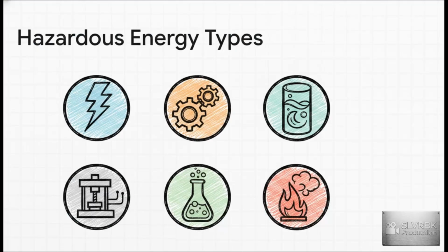Now, when you hear the phrase lockout/tagout, it's super common to picture a breaker box and think strictly about getting shocked. But the hazards are actually so much broader than that. Hazardous energy encompasses mechanical, hydraulic, pneumatic, chemical, and thermal energies. Just think of a massive pneumatic press that could suddenly cycle, or a hydraulic arm dropping out of nowhere, or maybe steam unexpectedly releasing from a pressurized valve. If any of these energies unexpectedly release, or if machinery suddenly starts up while someone is servicing it, it can cause severe harm. We have to control all of it.